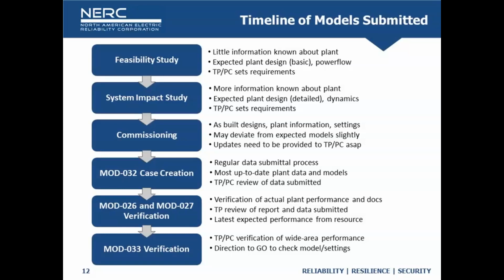We can get lost in conversations like: when I submit my interconnection request, I don't know the make and model of the facility, or what type of inverter is being used, so I don't have a model to submit in the feasibility study. Then at the system impact study, I'm a little more certain on the model type and plant configuration. By commissioning, everything is solidified. Working through the process, everything is actually fairly clear in the LGIA and LGIP, but it definitely needs more attention - it all goes back to that initial interconnection request. Any change to that request - make, model of inverter, plant configuration, plant capacity, all those things - requires a restudy. That's stated point blank in the requirements, but it's just not happening in the actual interconnection process.